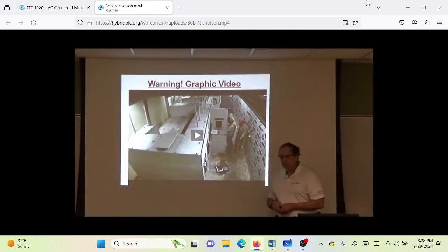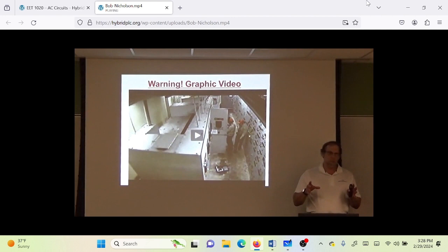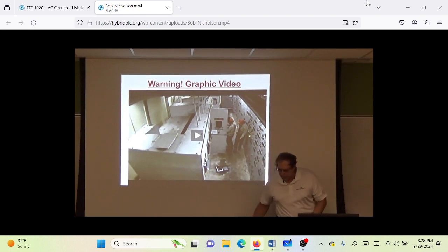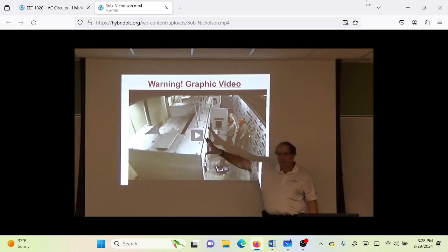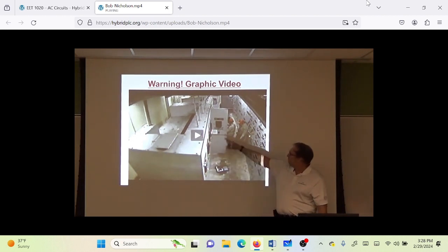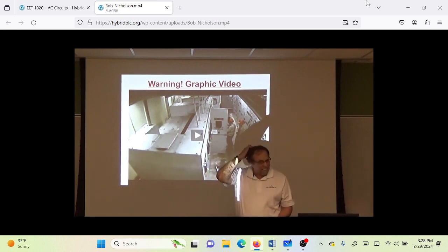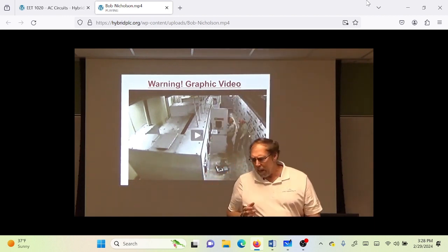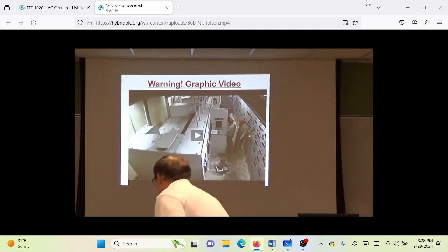This guy right here is putting a large breaker into a panel. Here's the second. What's going to happen is this breaker is going to fit. There's going to be a short. He's cranking a handle. The breaker is slowly going in. It's going to touch the live bus. If there was nothing wrong with the breaker, there wouldn't be a problem. There is a short in the breaker. So somewhere outside the building, the transformer is going to deliver fault current. And it's going to come out of the box. It's not going to be a mannequin now. It's going to be a person. So now, he doesn't get to go home.